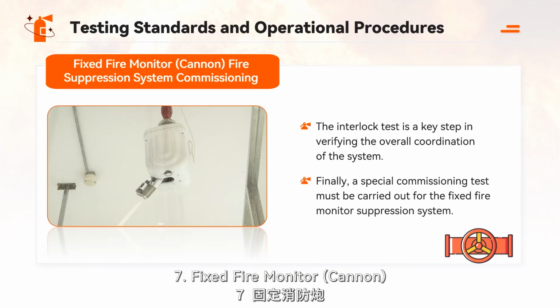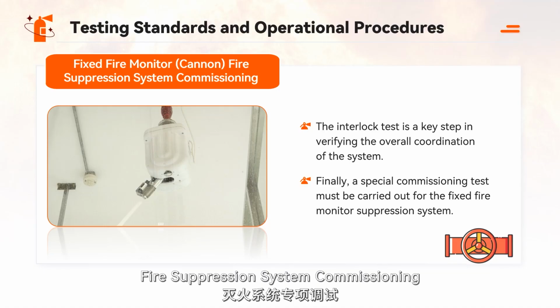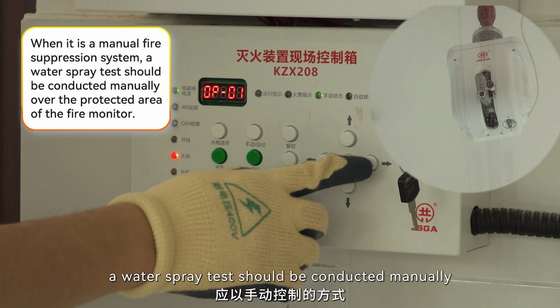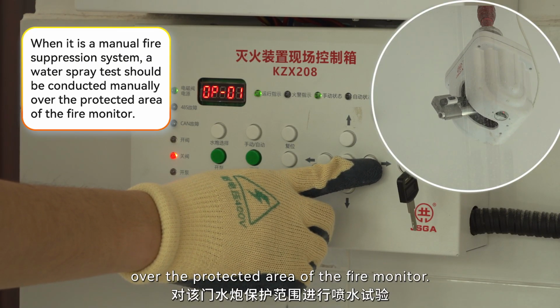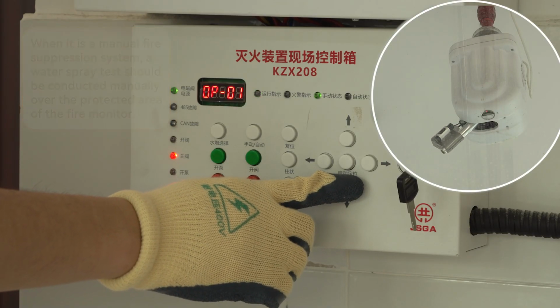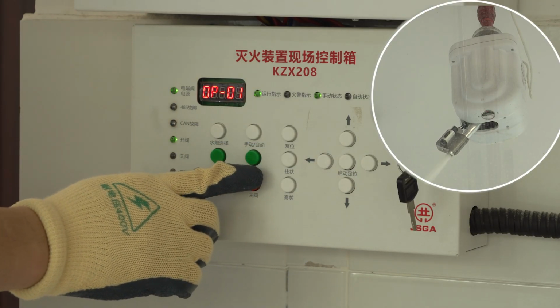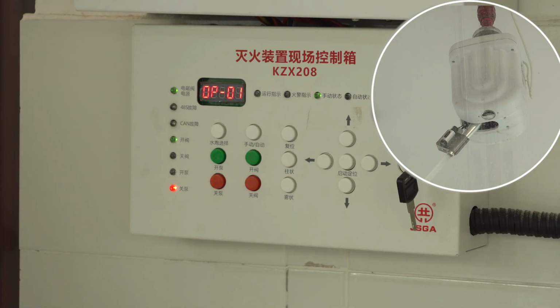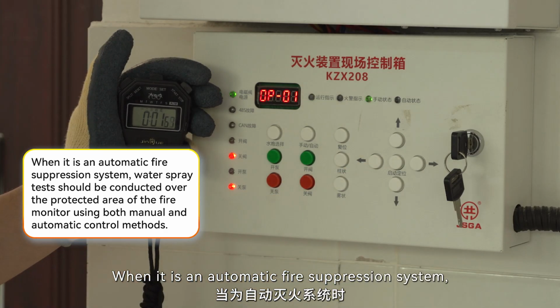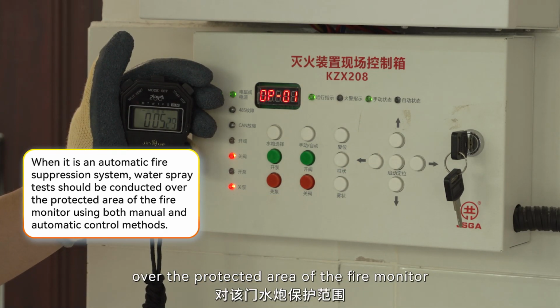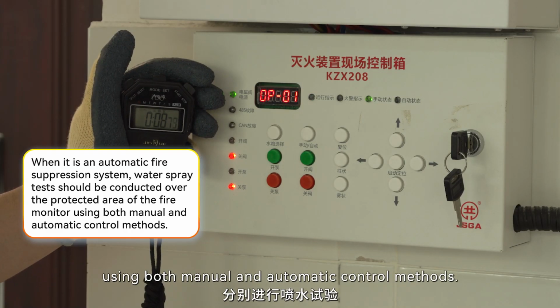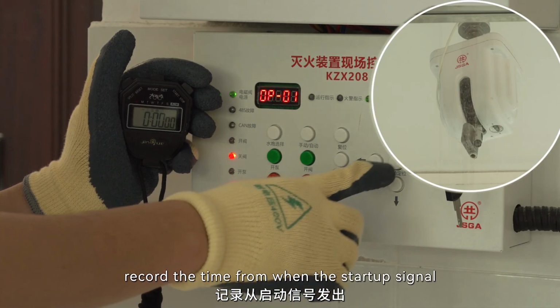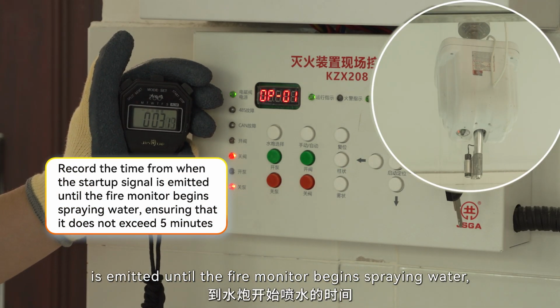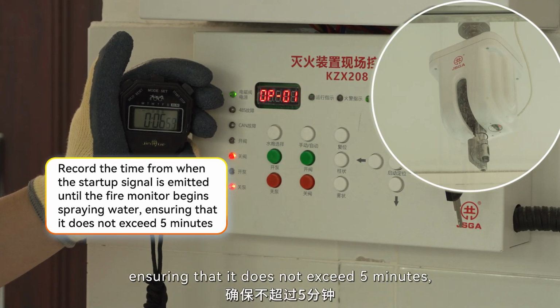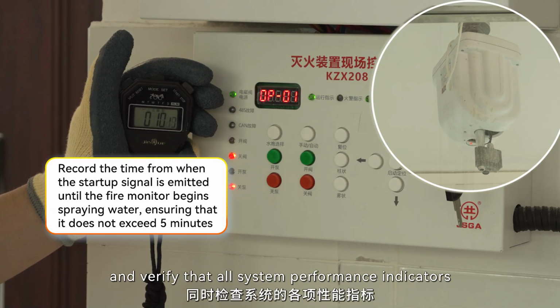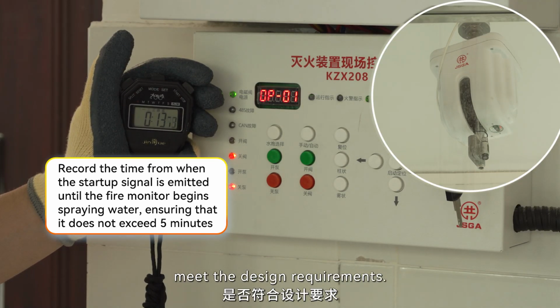7. Fixed fire monitor, Cannon, fire suppression system commissioning. When it is a manual fire suppression system, a water spray test should be conducted manually over the protected area of the fire monitor. When it is an automatic fire suppression system, water spray tests should be conducted over the protected area of the fire monitor using both manual and automatic control methods. During the test, record the time from when the startup signal is emitted until the fire monitor begins spraying water, ensuring that it does not exceed 5 minutes, and verify that all system performance indicators meet the design requirements.